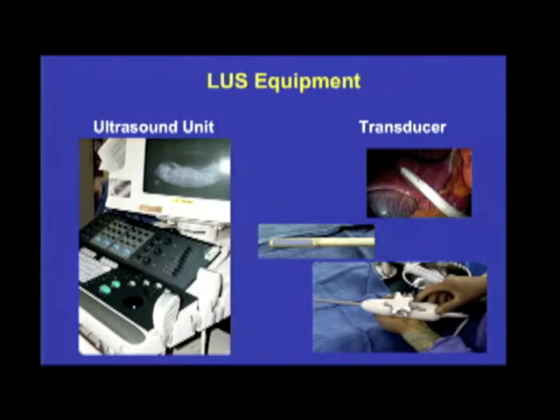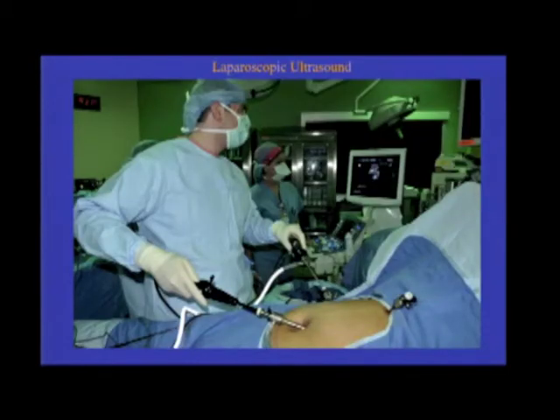This is a thing that we really need. You need to have a dedicated laparoscopic probe. I tend to gas sterilize all our probes instead of putting covers over them, so it takes a little while, and if you do one case and try to follow with another case, sometimes equipment can be a problem, so you really want to have several probes. But you have to be very careful because they're easily damaged. This is a typical setup.